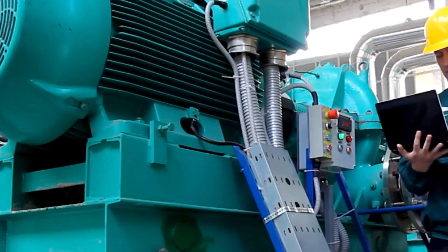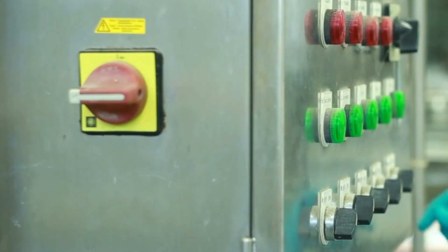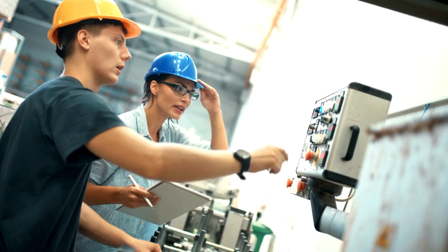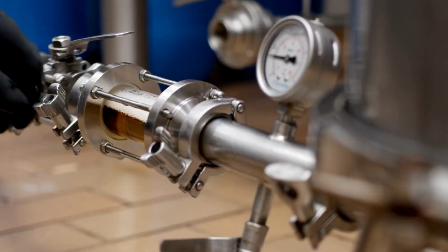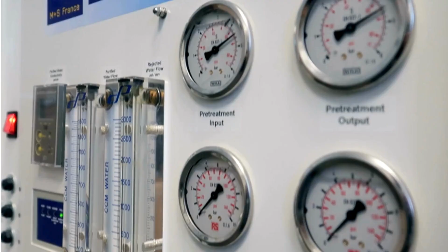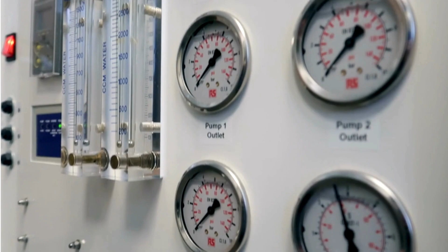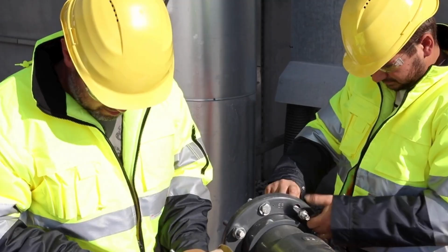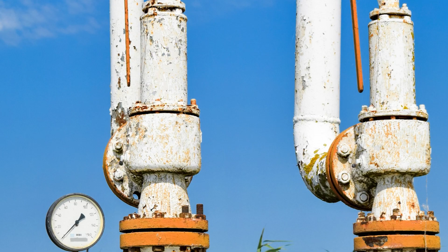Check for any mechanical issues as well as valve problems. Use manual overrides to open or close the valve if necessary. Look for chemical leaks, verify that the instrumentation is reading properly and has power. Check for leaks in pipes, and ensure that pressure relief valves haven't been triggered. You can learn a lot by looking at changes in pressures and flows in the affected area.